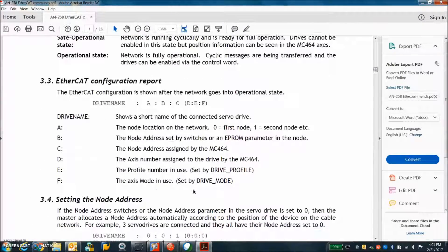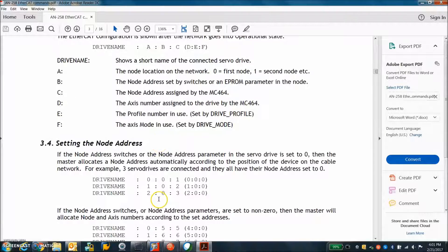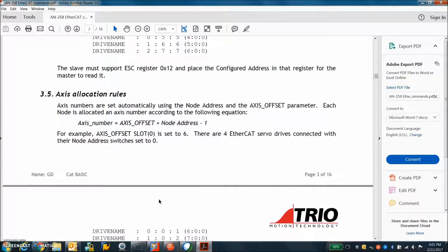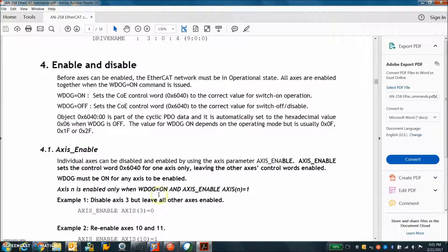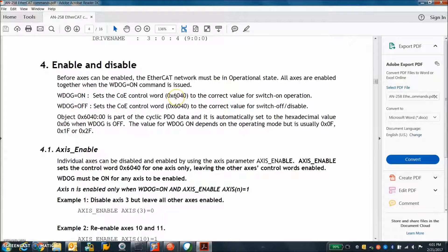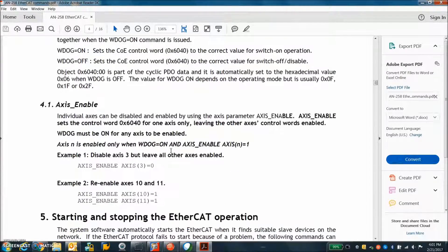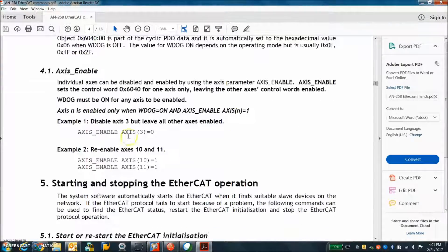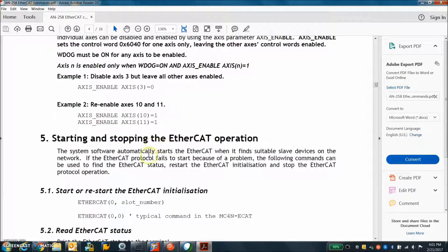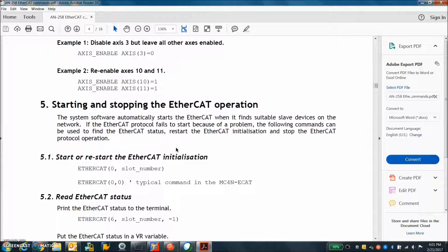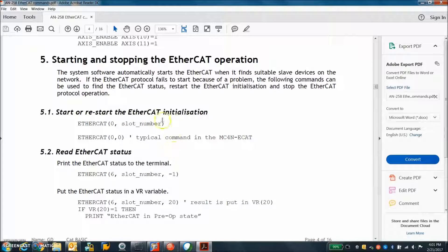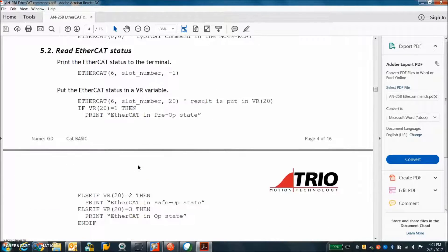So there's a definition of what this means here in the app note. Enable disable watchdog off and on writes to the COE, CANopen over EtherCAT, object 6040 which is the control word. So we can enable axes, disable axes, change modes. We can restart EtherCAT in different modes of operation, different slots.